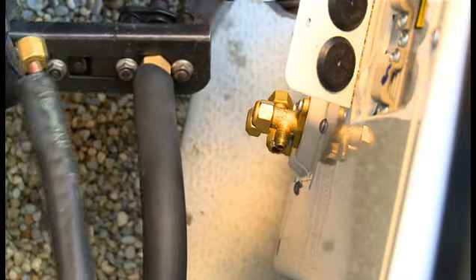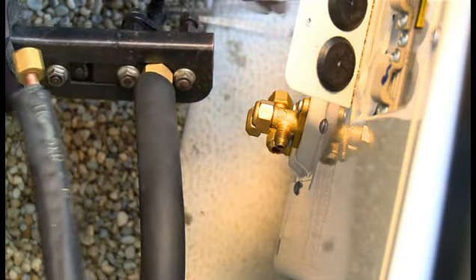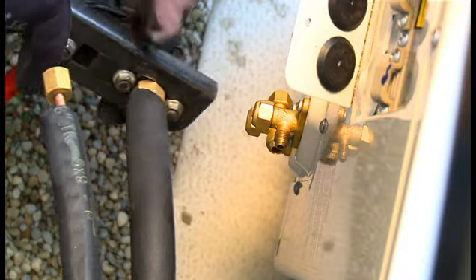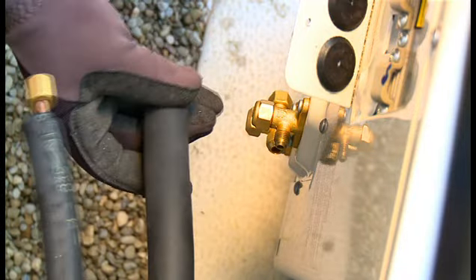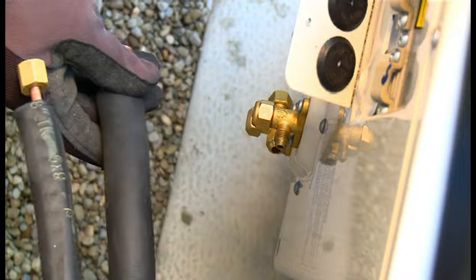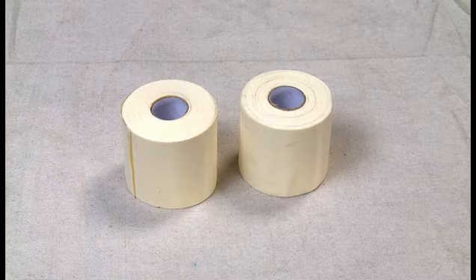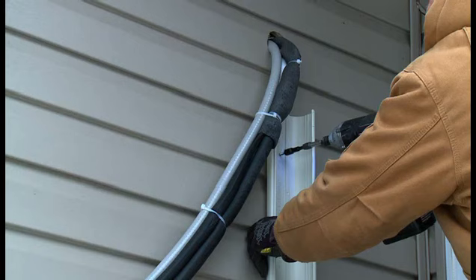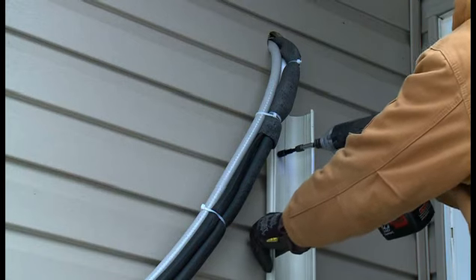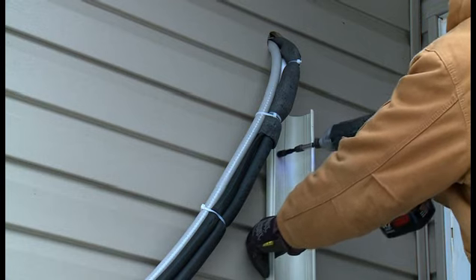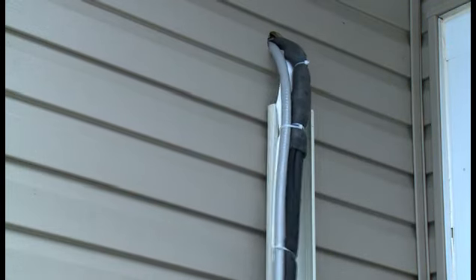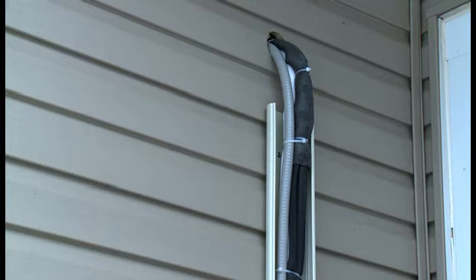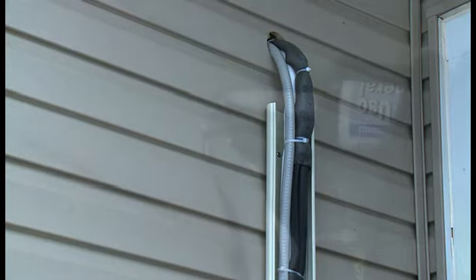If the refrigerant tubing is too long, cut it to the correct length or roll up the excess. If the tubing is cut, the ends will need to be flared before completing the connection. Line set all-season tape included with the appliance may be used to wrap the drain hose, line set, and conduit. However, if desired or recommended by code, a decorative line set cover and weatherhead may be used to house and protect the drain hose, line set, and conduit. These are available at most HVAC stores.